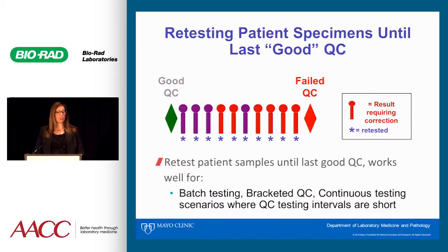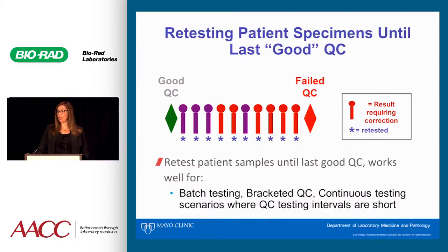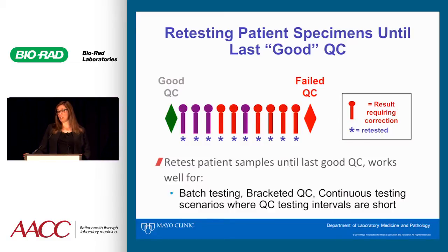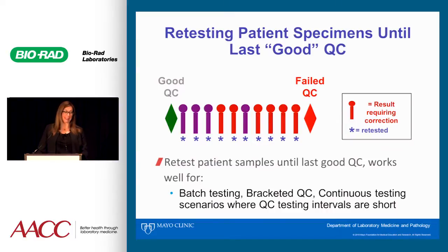This approach is good in situations where you're doing batch testing — maybe bracketed QC — or where the QC testing intervals are short and you're not testing very many patients between QC events, because then it's practical. However, in labs where we might do 200 to 400 patient samples an hour, this is not a practical approach.